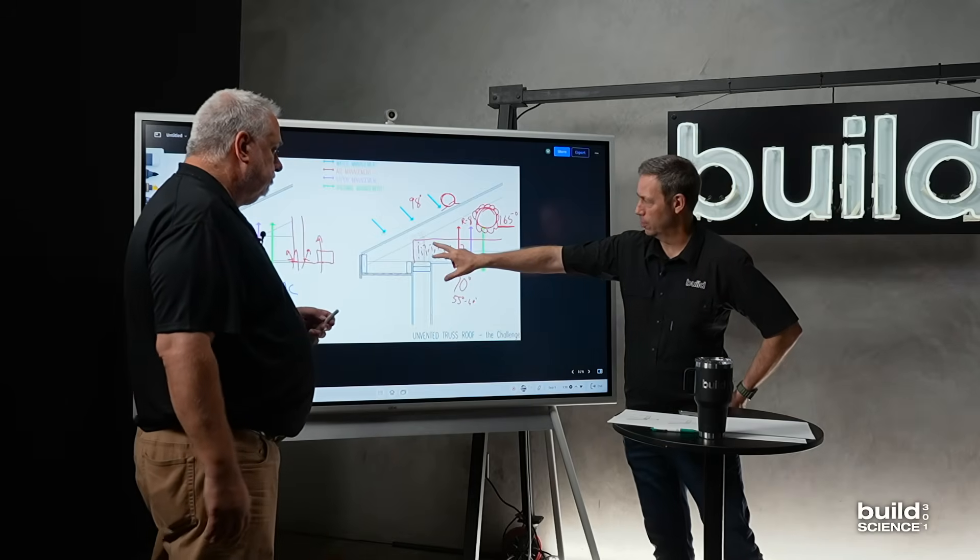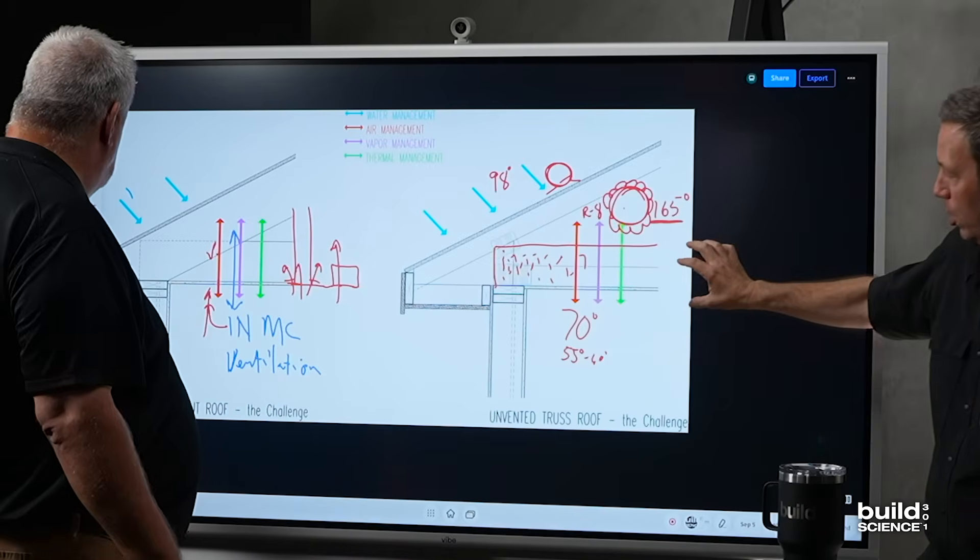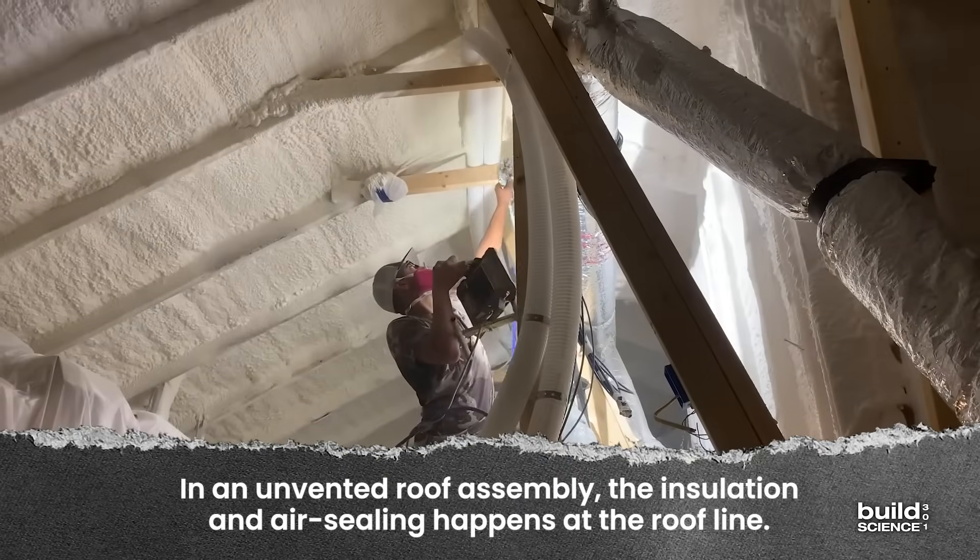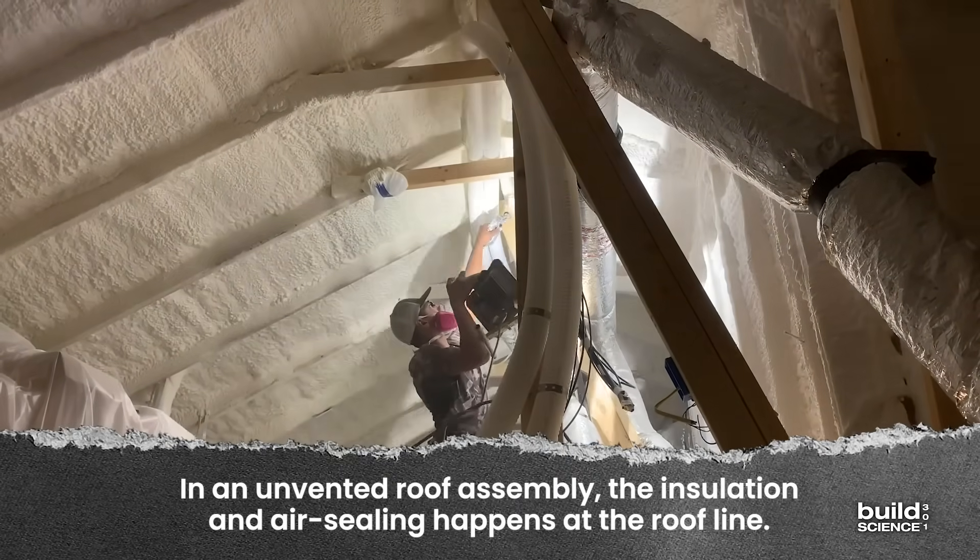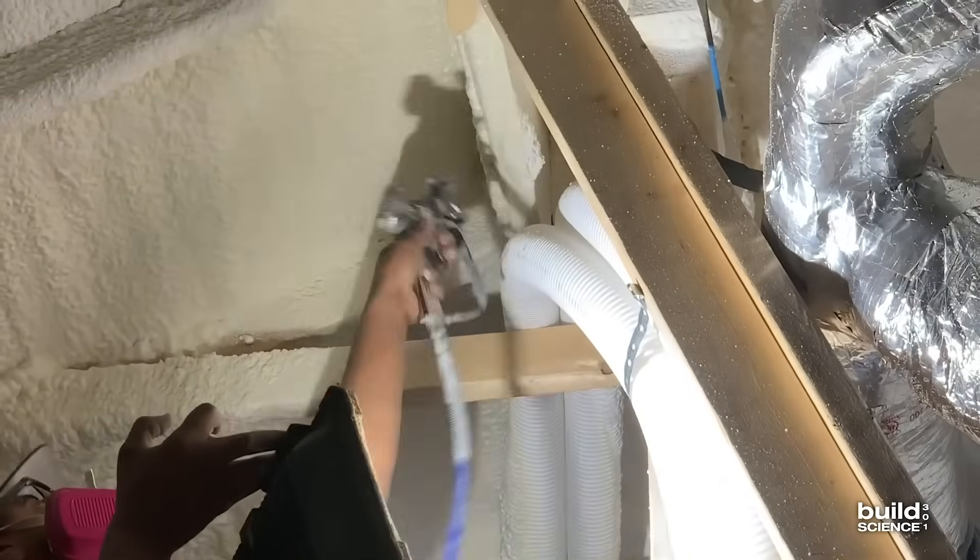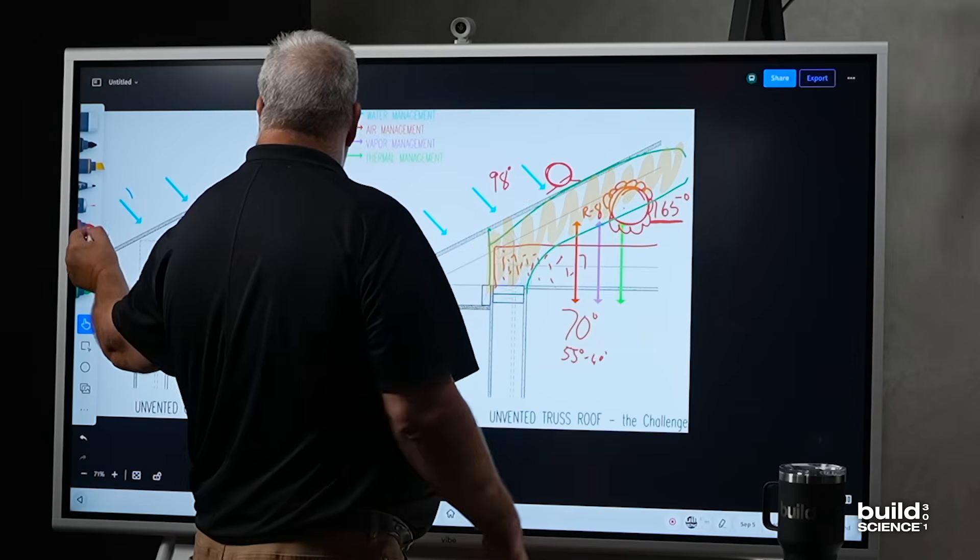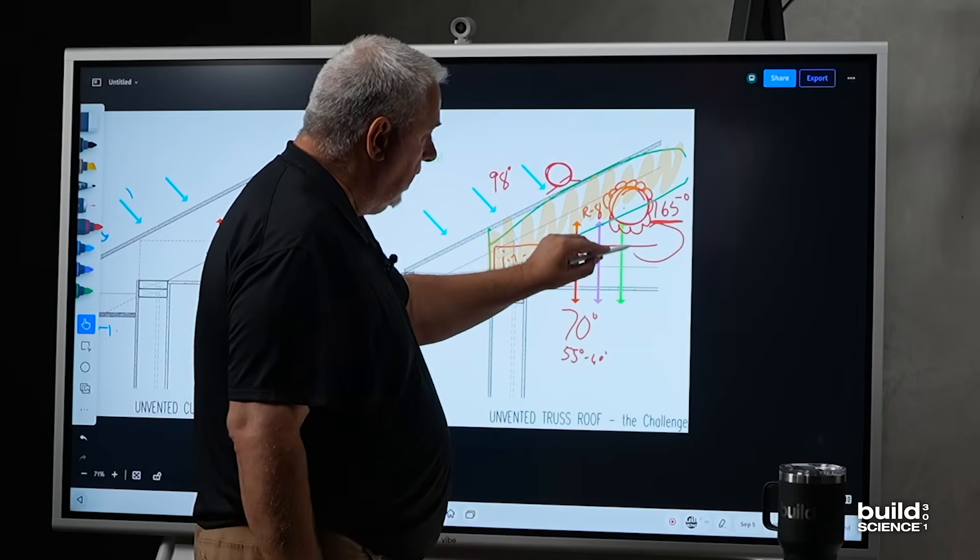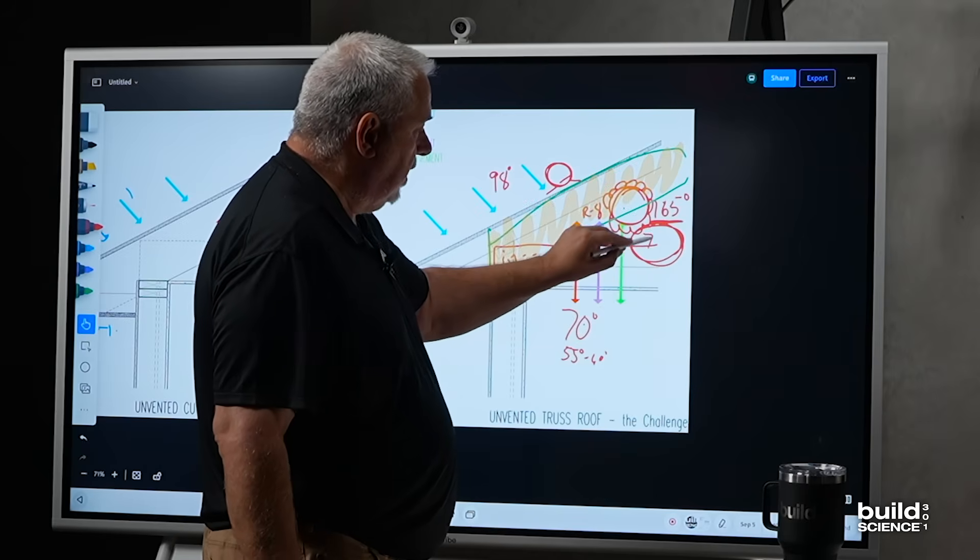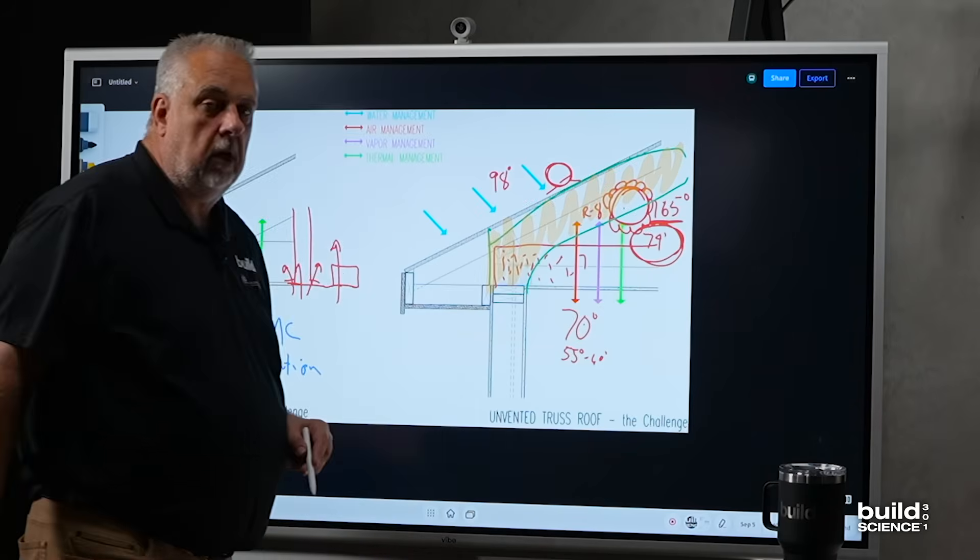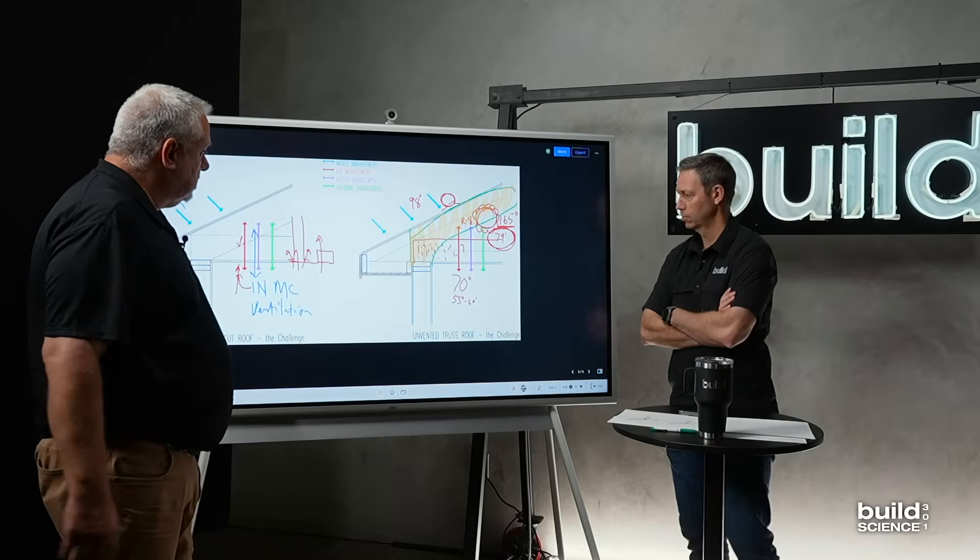Then an unvented roof assembly, instead of this insulation here at the drywall, we're actually talking about insulation at the roof line. We probably want to do something like that, where all of this is our insulation. Now, when I put that duct in and I put it in here, it's not 165. It might be 74 degrees up there. Far better system.